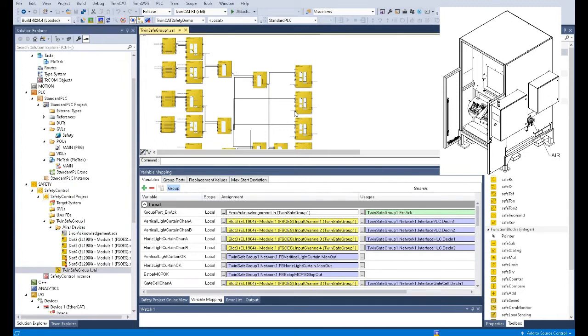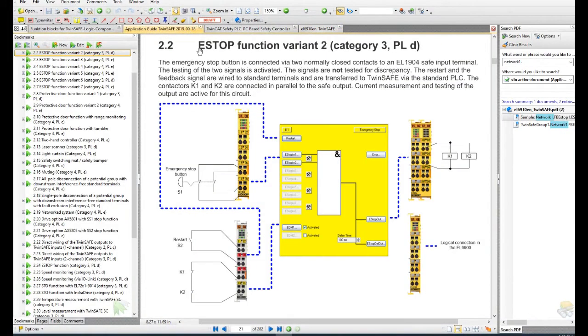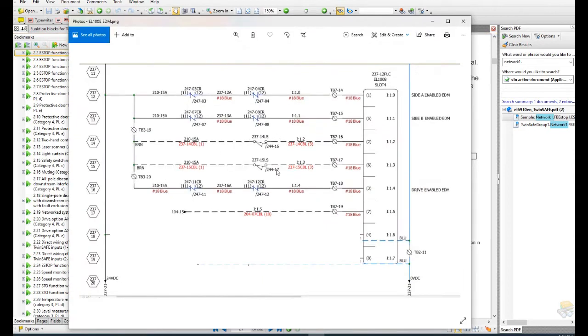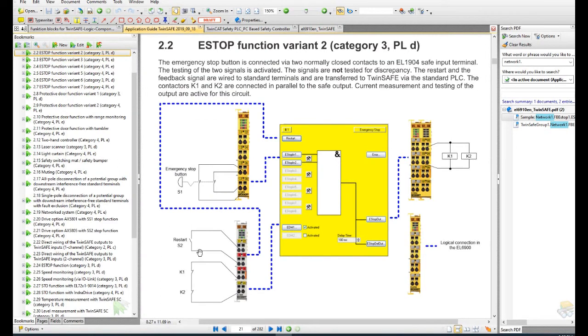The second signal is the EDM signal. According to our application diagram, for the e-stop loop we already programmed the safety input, safety output, and the core logic. However, we haven't connected the EDM signal area — the K1 and K2 come from the relay. This K1, K2 EDM signal is a normally closed signal coming from the relays, and both signals come from the standard card. For the reset, this reset signal also comes from the standard PLC. For the EDM signal, the actual drawing shows the drive relay using two relay outputs as a normally closed feedback signal to the standard signal card. The third example is the restart signal.